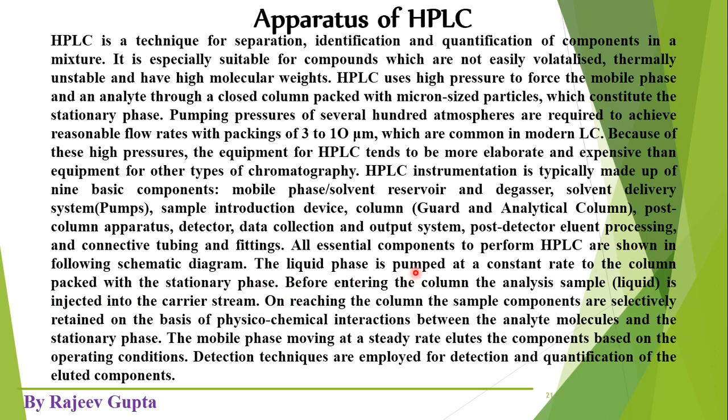Due to the presence of these pumps, this liquid phase or mobile phase flows with a constant rate, almost 1 ml or 2 ml per minute through the column. Before entering the column, the analysis sample or liquid is injected. Means just before entering the analytical column or guard column, we inject our liquid sample into this carrier stream or mobile phase.